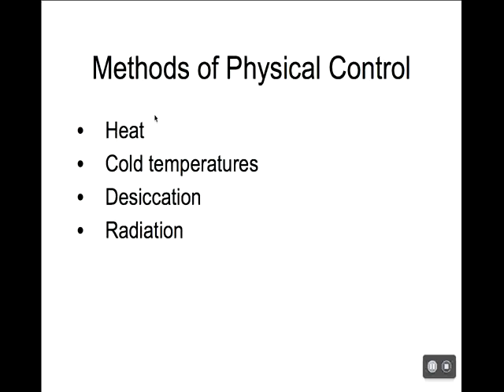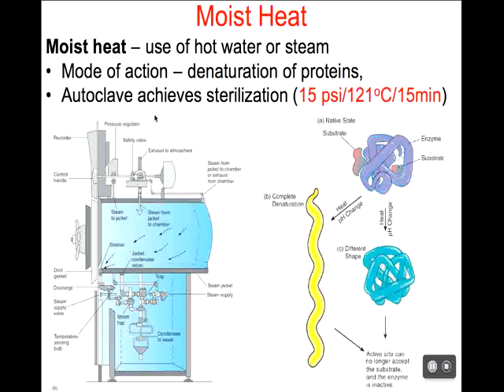Starting out with heat, I want to talk first about moist heat. Moist heat is using hot water or steam, and you're raising the temperature above the max growth temp. This is microbicidal. It does kill off microbes. Now, how does it kill off the microbe? It does that by denaturing its proteins. Remember, proteins are only effective when they are shaped correctly. If you either change the pH dramatically or increase the temperature, they will change their shape and they're no longer active.